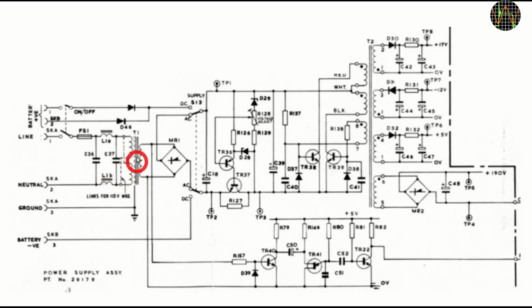We have the usual mains transformer followed by the rectifier and a smoothing cap to convert it to DC. But since the meter can be powered from AC mains or from an external DC source, what happens next is that the DC from either input is fed into a regulator made of TR36, TR37 as the power transistor, and the Z diode D29. A bit unusual to have an NPN power transistor on the negative side, but why not? The regulator is set to produce 9.5 volts, whatever the input, which then feeds an oscillator producing a high frequency AC going to another transformer.